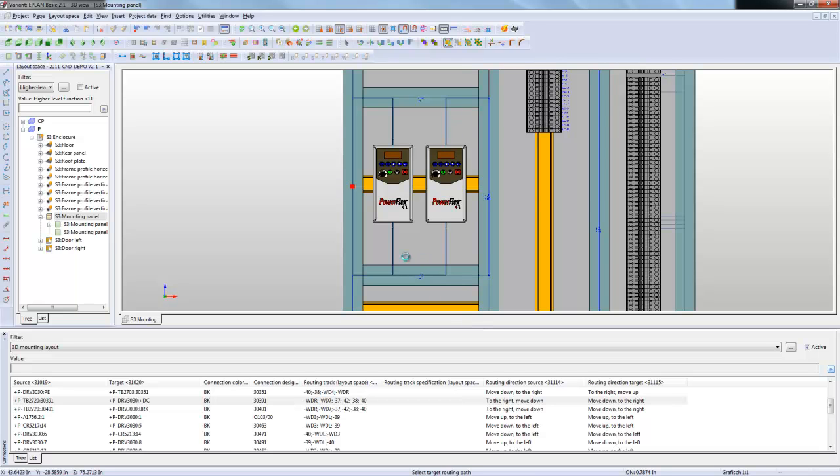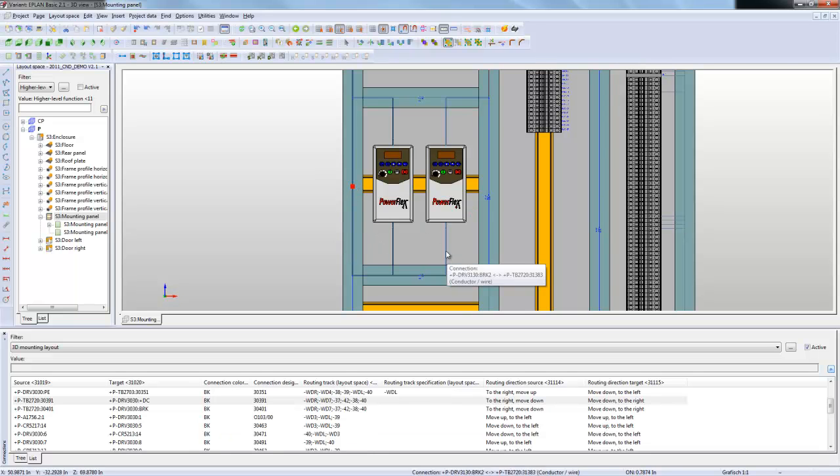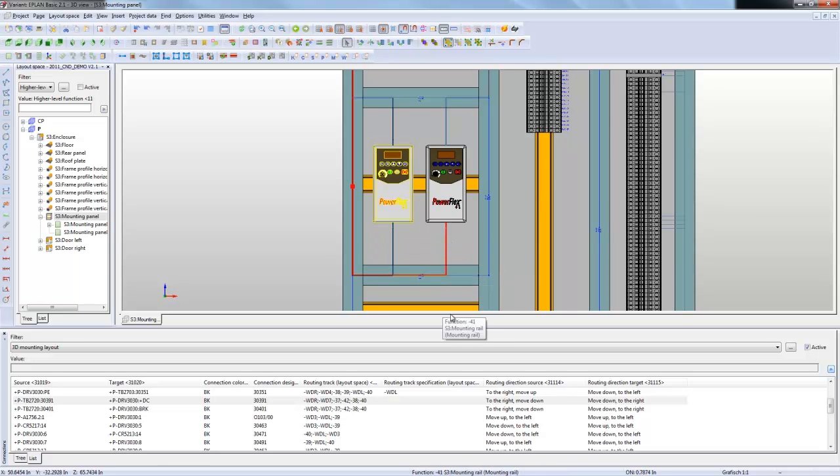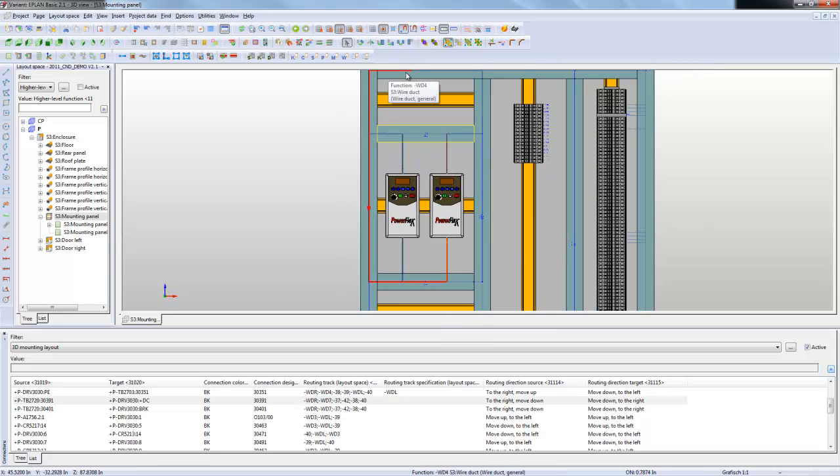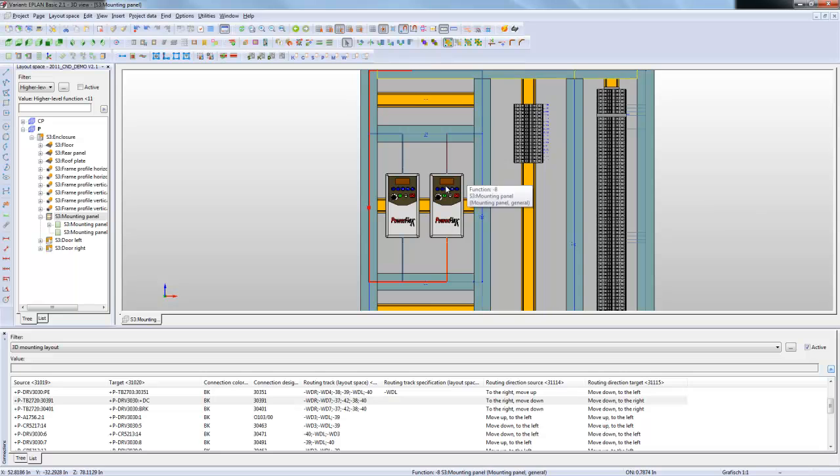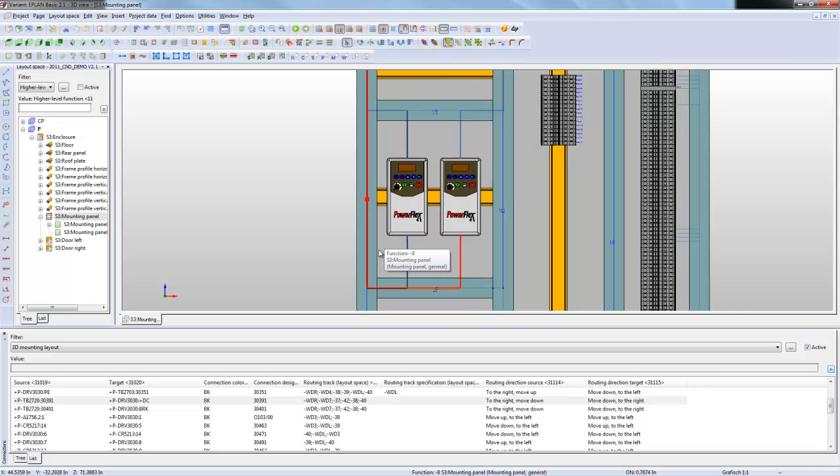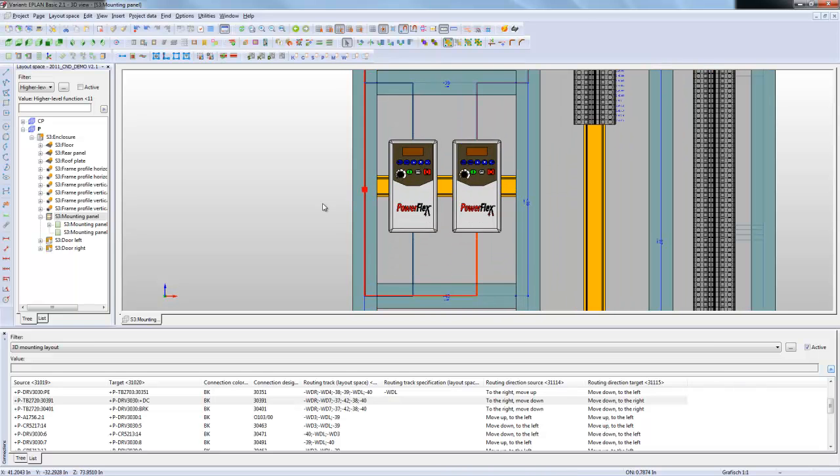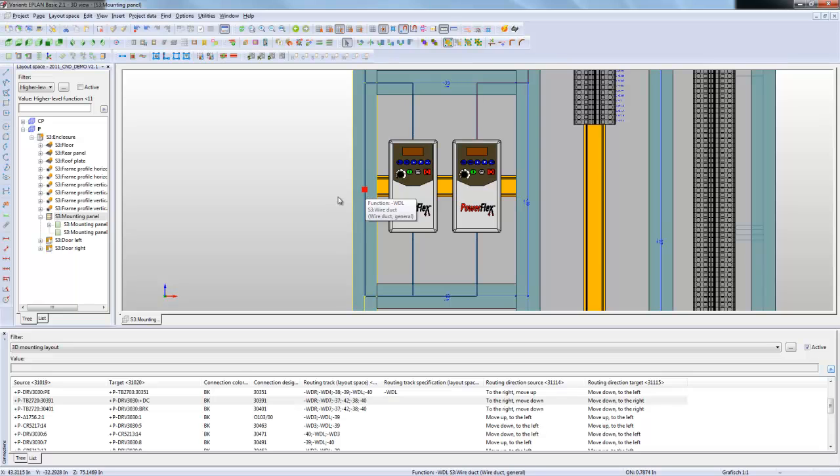Now you'll notice that all the wires that I have connected to that routing is going to go through these other sides. He changed the routing and made this guy go this way as opposed to going through this wire duct which it was going before. One thing that you'll notice is it's giving you this little red dot. This red dot is telling you that this wire duct is pretty much almost filled to capacity.